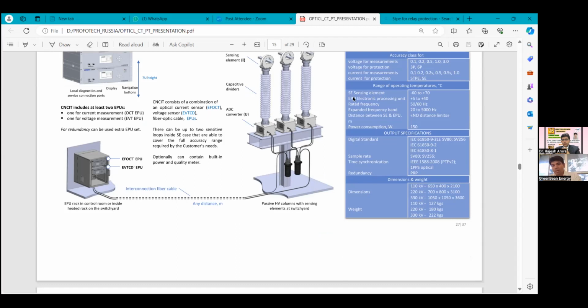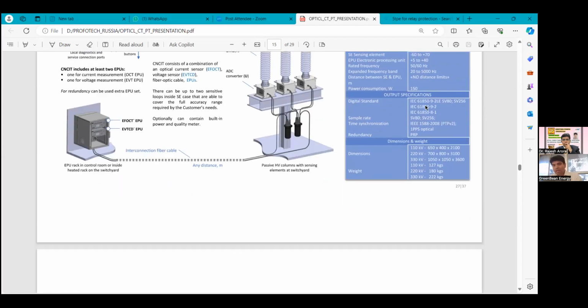So this is the same parameter, and it can measure from 20 Hertz to 5000 Hertz. Cable can be laid from any distance, and the digital standard is the same, IEC 61850-9-2. The dimensions here are: 110 kV, 650 by 400 by 2100; 220 kV, 700 by 800 by 3100; 330 kV, 1050 by 1050 by 3600.